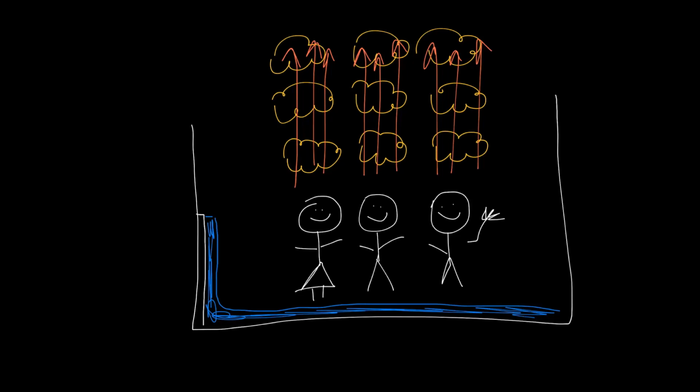Return air inlets must be located well above the breathing level of the occupants and should also be amply sized. A face velocity of 200 feet per minute or less is recommended to allow the contaminated air easy passage into the return air plenum.